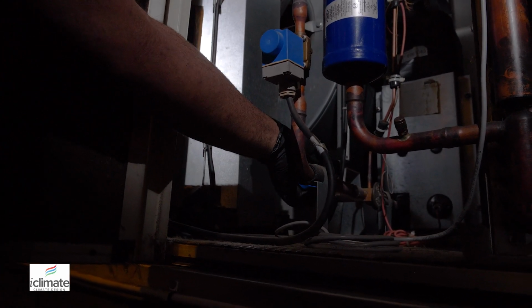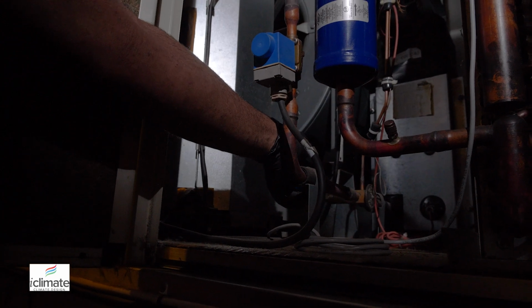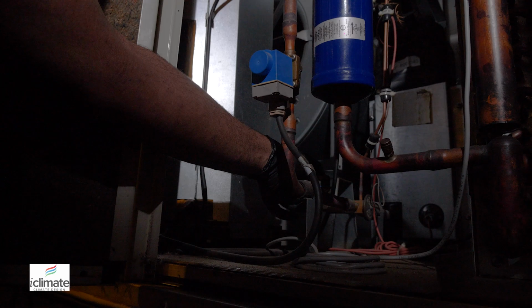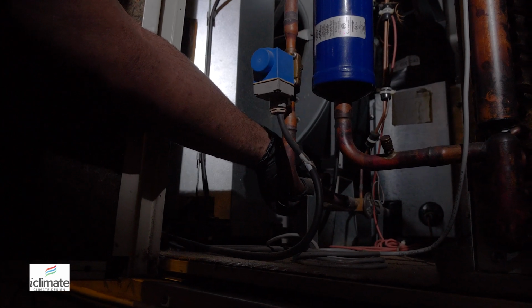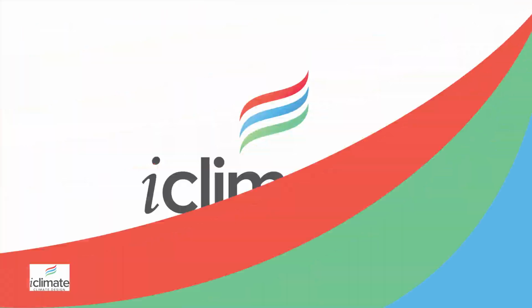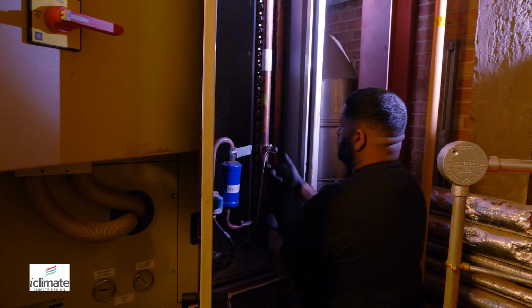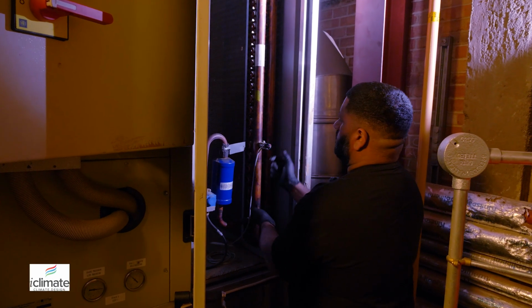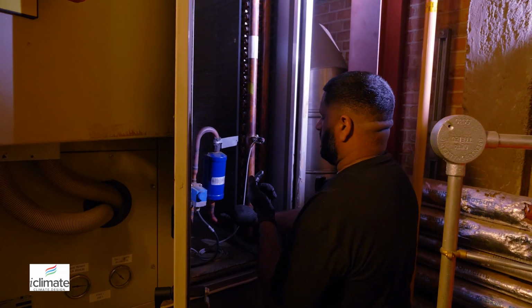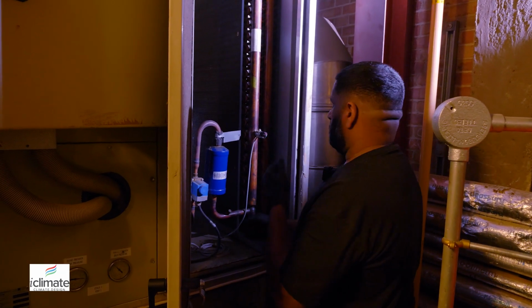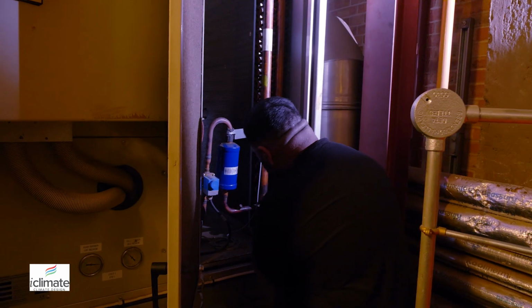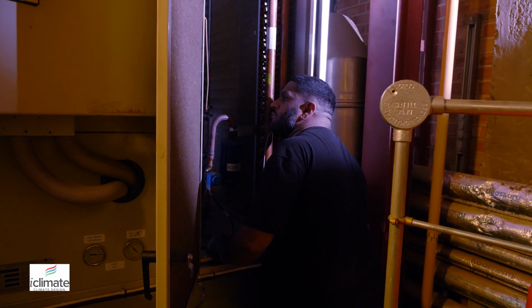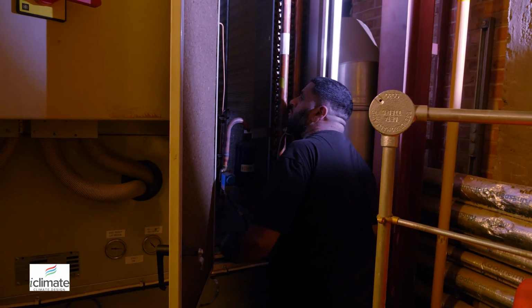This normally has a litmus paper inside. It tells us the moisture content within the refrigeration circuit. So if you have moisture, it's yellow, and if you're free of moisture, then it's green, which gives you an indicator. This also gives you an idea of how full the liquid line pipe is. Under 100% capacity, this should be a glass filled with no bubbles. Bubbles indicate movement and indicate the liquid line not being at 100% volume, which in some instances could mean it's short of refrigerant.